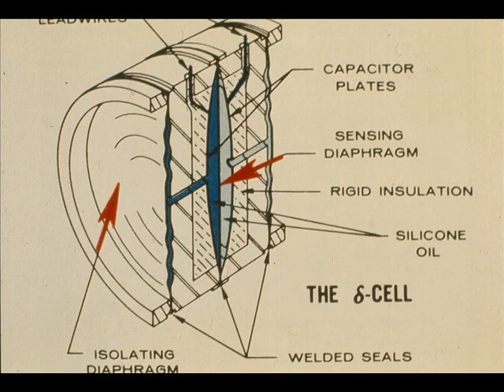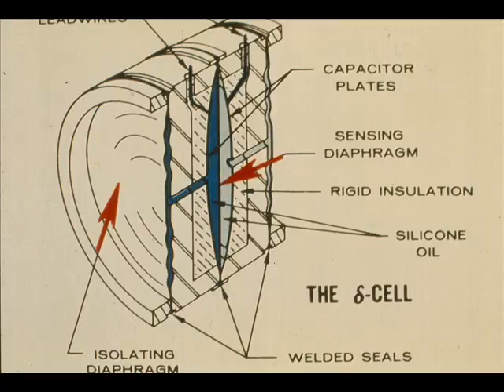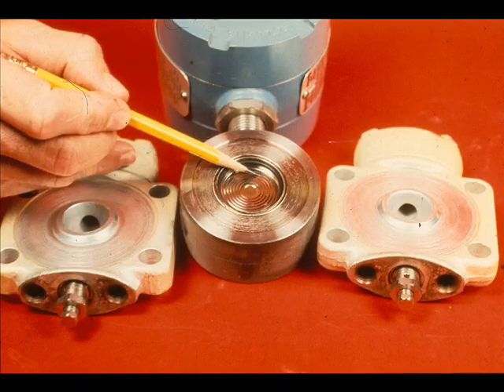The high and low pressure sides are filled with silicone oil out to the isolating diaphragms. The sensing diaphragm isolates the high and low pressure fills. The isolating diaphragms isolate the process fluid from the silicone oil.